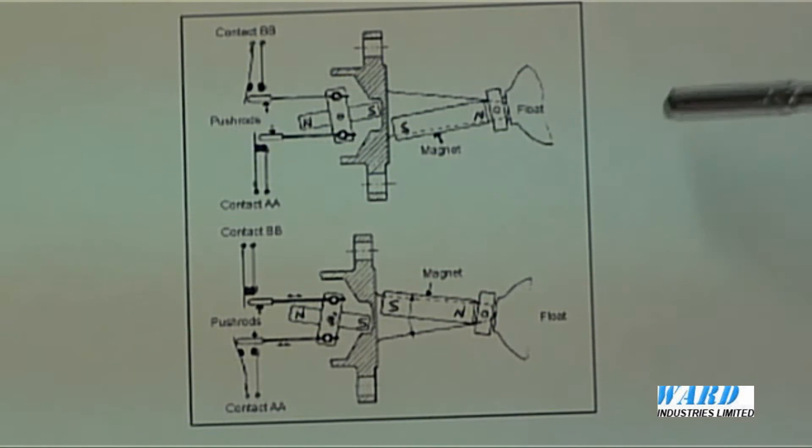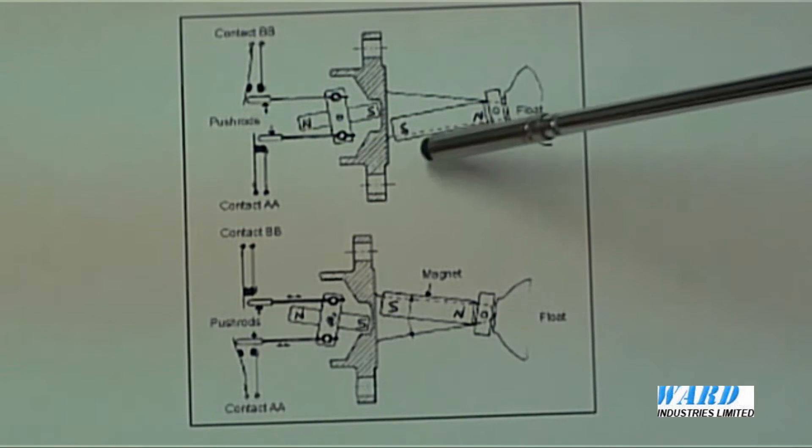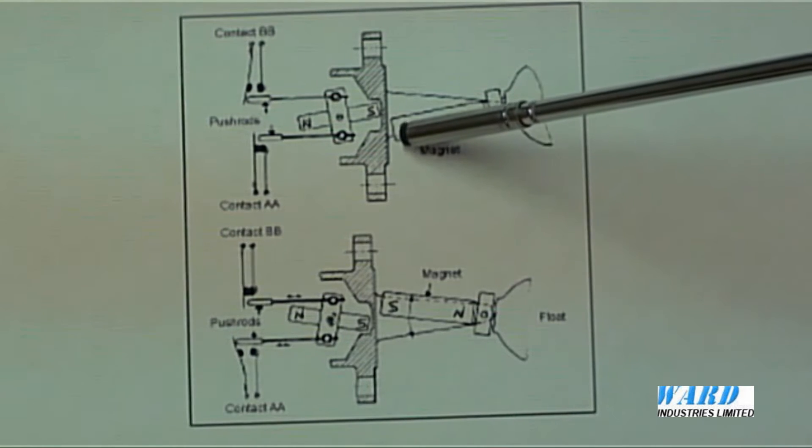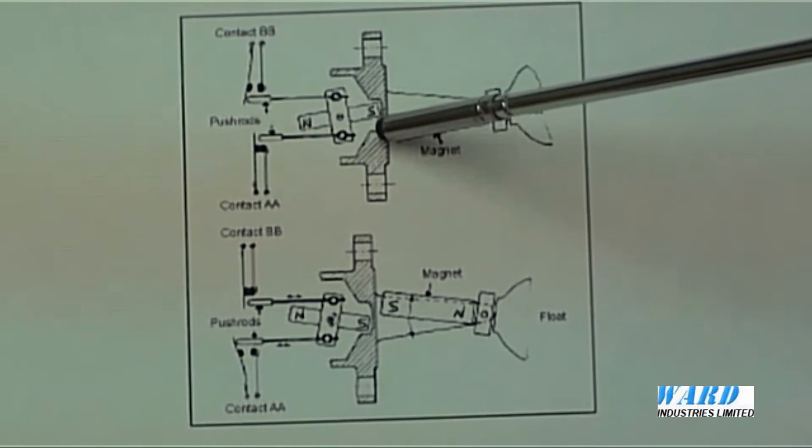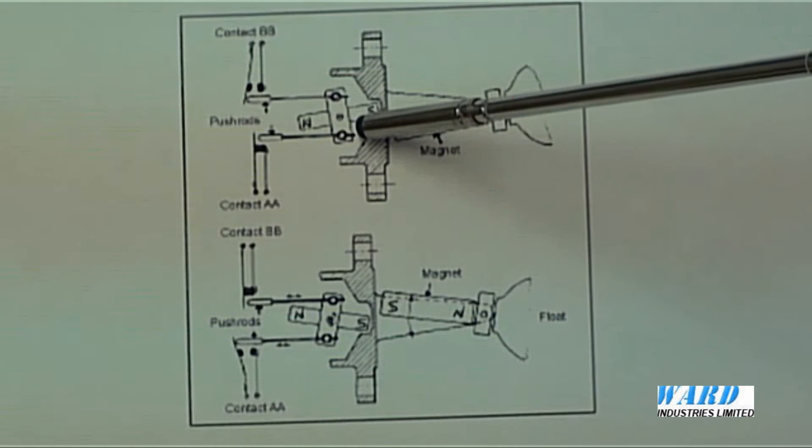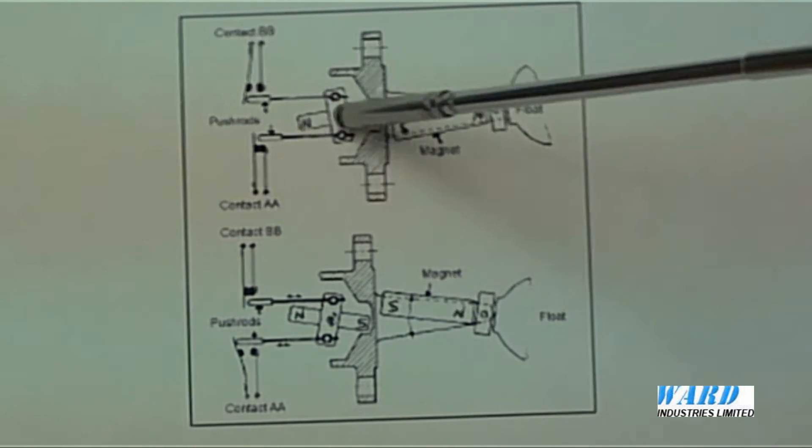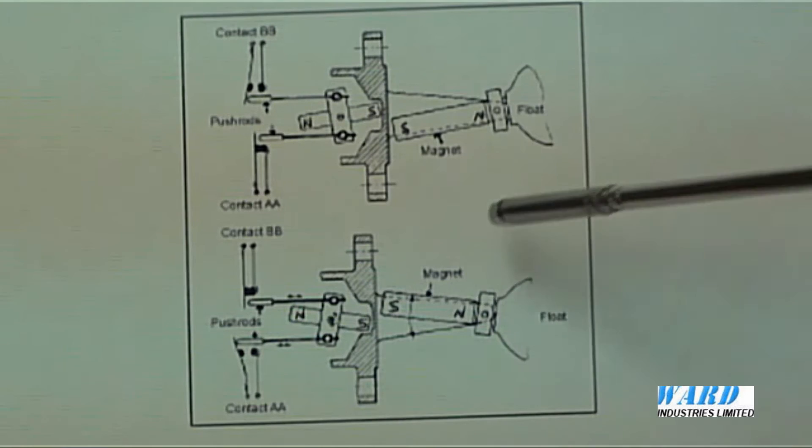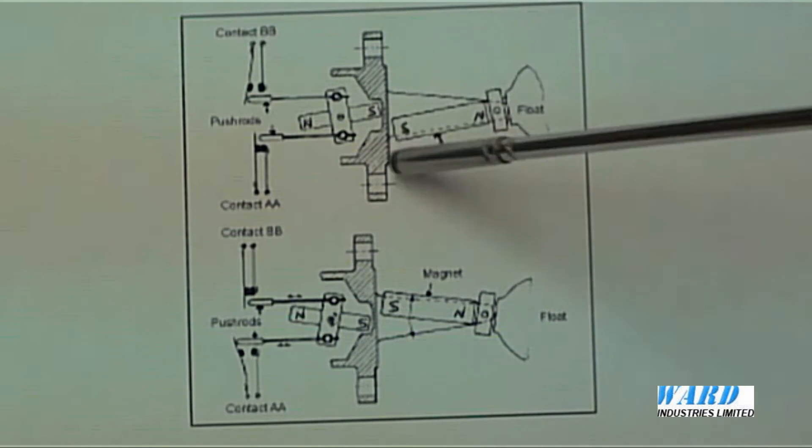Consequently, a change in liquid level, here you can see the float in the high level position. As that falls, this magnetic pole will face directly the same pole in the switch head mechanism through a non-magnetic diaphragm here.